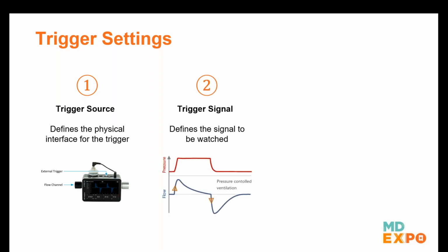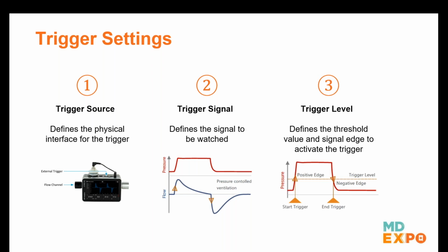Then the second parameter is a trigger signal. Typically you can select between a pressure curve to be watched for the trigger or a flow waveform. And the third parameter we will talk about is the trigger level. This specifies the threshold when the trigger should be activated. And beside the value itself, we also need to tell the analyzer whether it should trigger when this threshold is reached on a rising edge of the waveform or a falling edge.